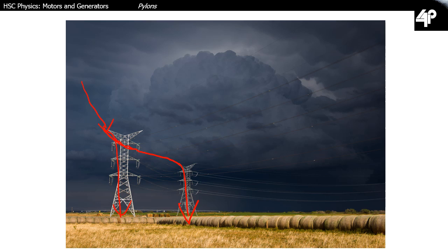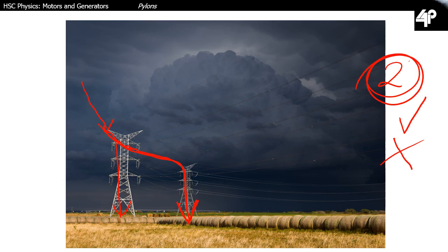Now, if the static line doesn't reach the next pylon, at least as the last method of protection, it will be grounded at the substation where the static line eventually ends up. So here's the important thing to remember: the two key differences between the static lines and the transmission lines. Firstly, the static line is connected to the pylon, and the transmission lines are well insulated, so no electricity can flow between the transmission line and the pylon. Secondly, the transmission lines should always be carrying electricity, while the static line normally carries no electricity whatsoever unless it's been struck by lightning.